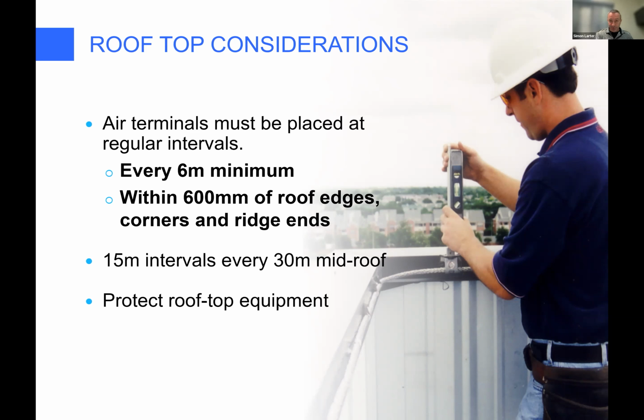In the mid-roof, we relax those spacing considerations because you don't have a counter leader developing as easily from a flat surface. So then we relax the spacing of lightning rods to every 15 meters. So that's a 15-meter grid on a roof. That's a typo. Ignore that 30 meters in that second item there. 15-meter intervals in a wide flat mid-roof.